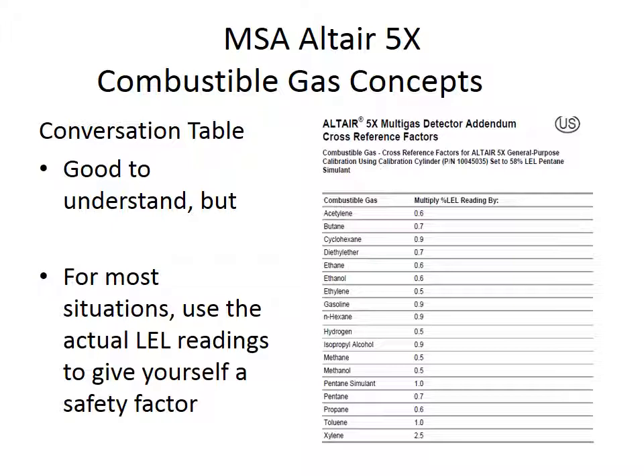And hopefully, let me try to explain this. The meters are calibrated on pentane simulant gas. So the sensor for combustible gas can't specifically tell whether it's picking up natural gas, a gasoline situation, or some other combustible gas situation. It just knows, the way the sensors are set up, that it's got a combustible gas coming in. It's been calibrated on pentane, so it gives you that reading based on what the LEL for the pentane simulant gas is.